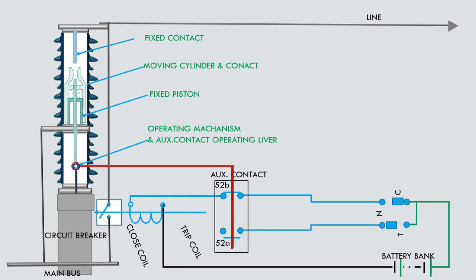This is a picture of a TNC switch or control switch. When at neutral, no pulse creation occurs. When its handle is turned toward trip, a tripping pulse goes to the trip coil. When its handle is turned toward close, a closing pulse goes to the closing coil.